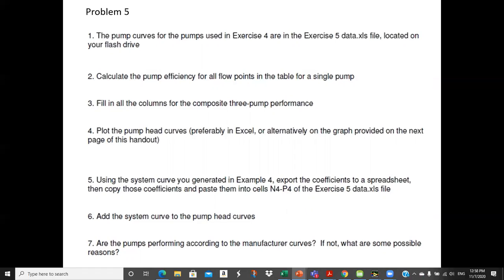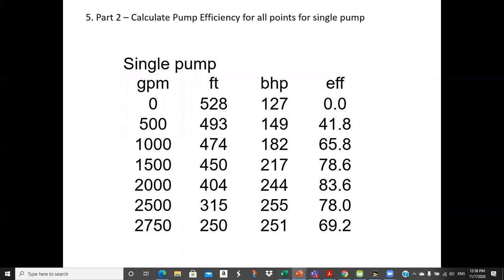Add the system curve to the pump head curves, and are the pumps performing according to the manufacturer curves? If not, what are some possible reasons? So we have to do all that. Okay, well, this is the calculated efficiency. This is what you should get.